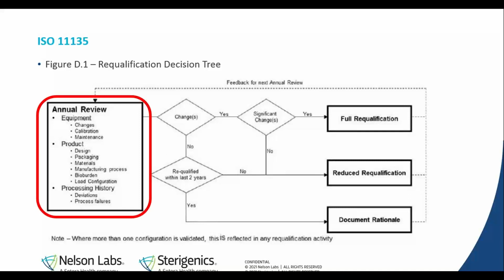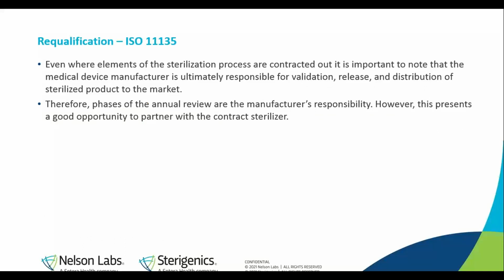So I'll highlight specifically this information on the left side of your screen for the annual review. What we want to review is, first of all, the equipment, secondly, the product, and lastly, the processing history. And we'll go over that in a little bit more detail. Even where elements of the sterilization process are contracted out, it's important to note that the medical device manufacturer is ultimately responsible for the validation, release, and distribution of sterilized product to the market. Therefore, the phases of this annual review are the manufacturer's responsibility. However, this presents a great opportunity to partner with your contract sterilizer to obtain all the information that's necessary for the process during the annual review.